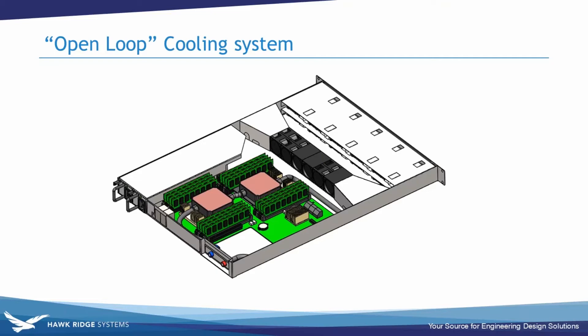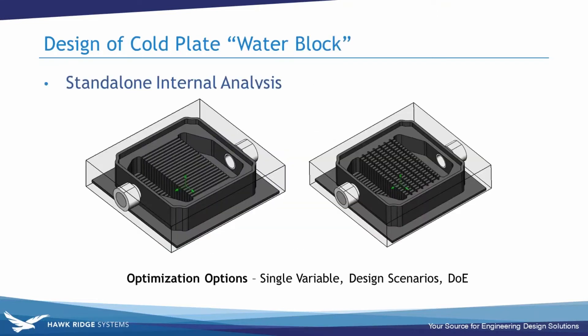Now let's move to liquid cooling setup. First, I want to look at an open loop system where the coolant pump and radiator are external to the server rack, and then we'll look at a closed loop system where the pump and radiator are within the server. Before designing the whole system, I want to look at the subsystem level first — specifically designing the water block for heat exchange to the CPU using liquid coolant. This procedure is also applicable to designing a heat sink for an air-cooled system; it's a very similar workflow at the part level.